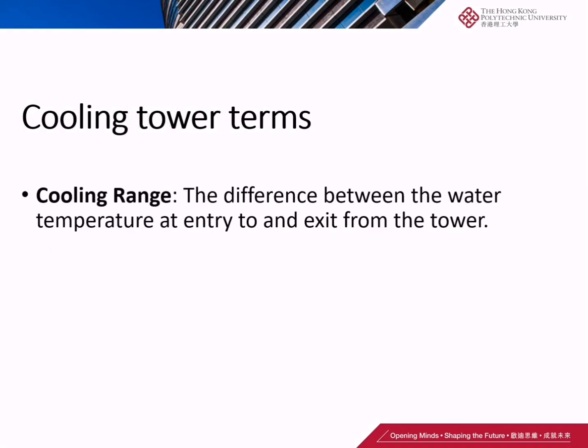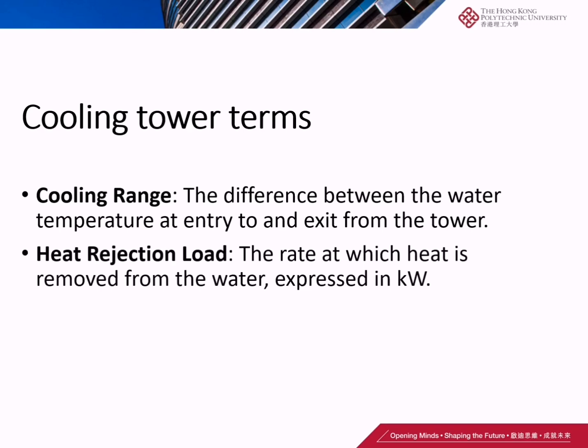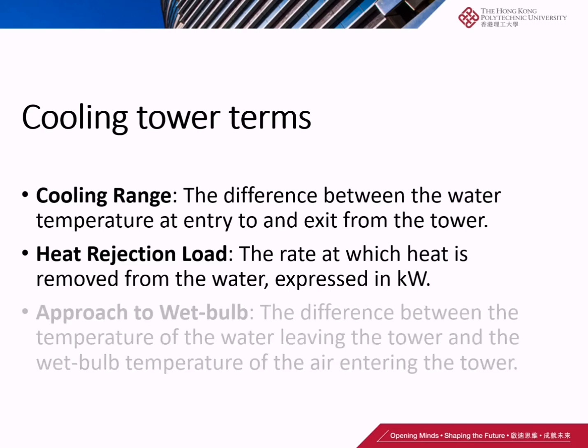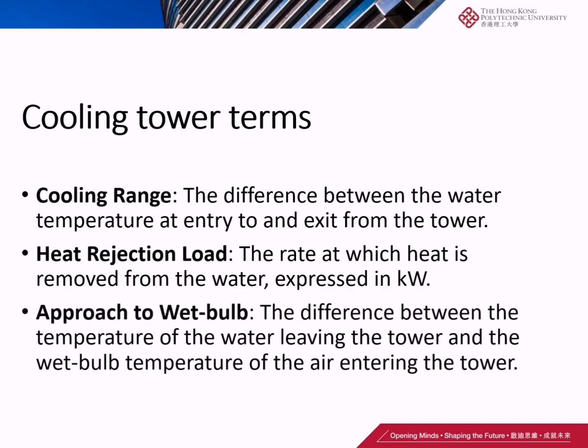There are some cooling tower terms worth mentioning. Cooling range is the difference between the water temperature at the entry to and the exit from the tower. Heat rejection load is the rate at which heat is removed from the water, expressed in kilowatts. Approach to wet bulb is the difference between the temperature of water leaving the tower and the wet bulb temperature of the air entering the tower.